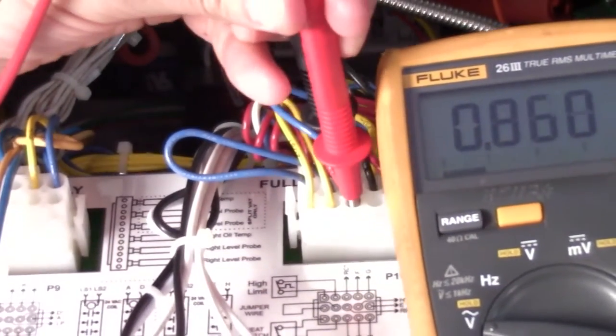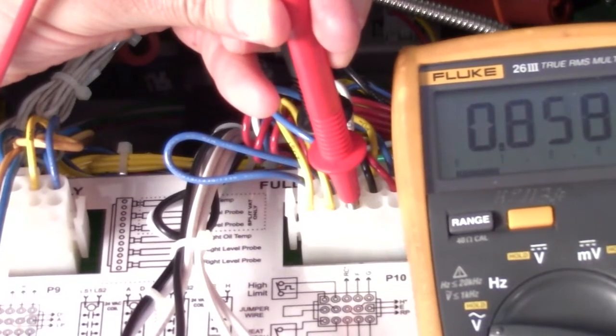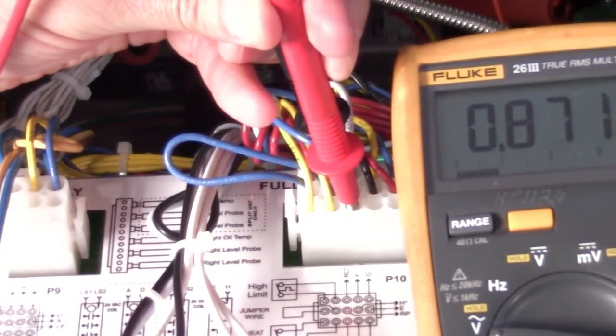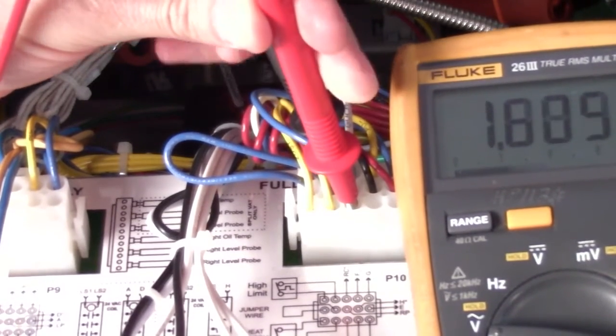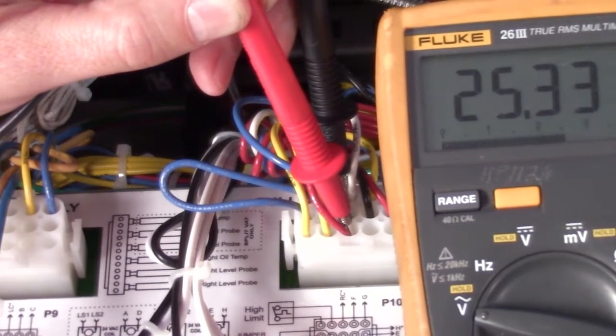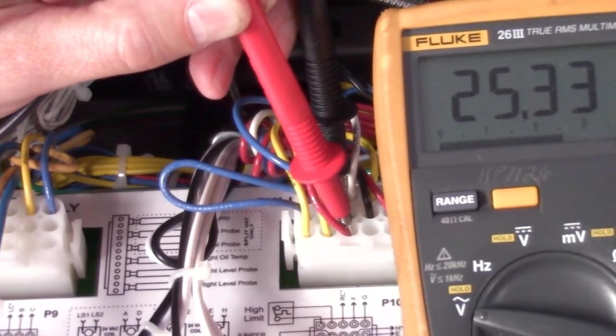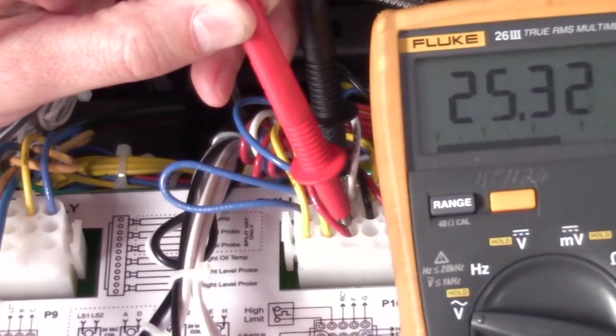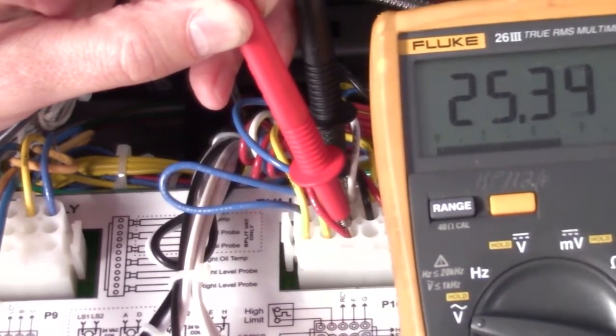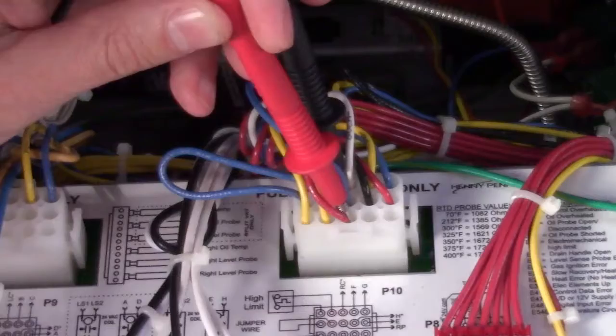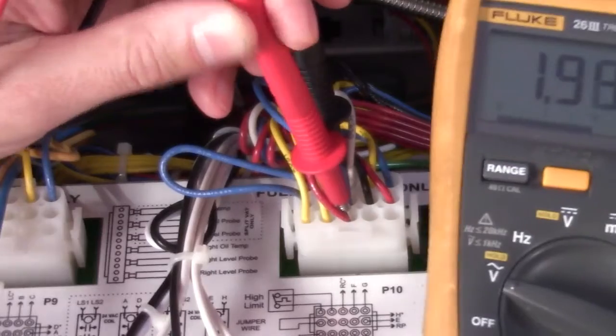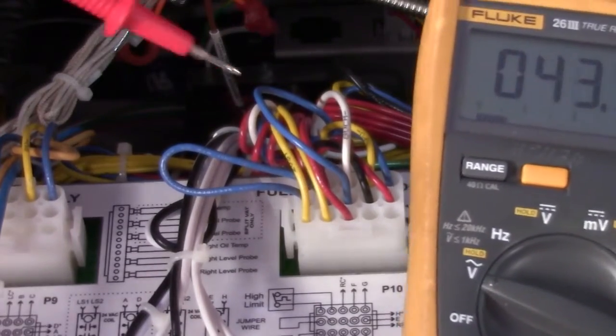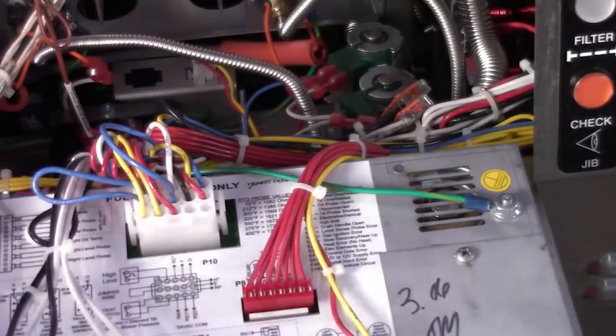And right now, we don't see anything because my green light's not on, it's not calling for heat. So let's wait and see. There we go, relay closed, it's sending voltage out. And we know then that we're sending our voltage out to our main burn on our gas valve. If we know that we have our voltage going out, one of the things you want to make sure you do, where you can check it, is you can also go down into the gas valve.